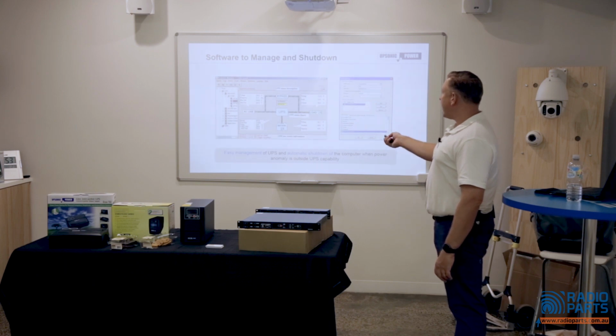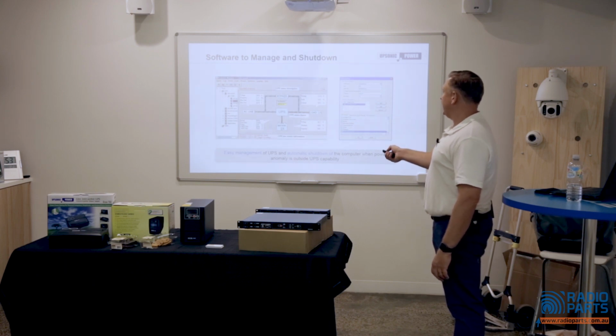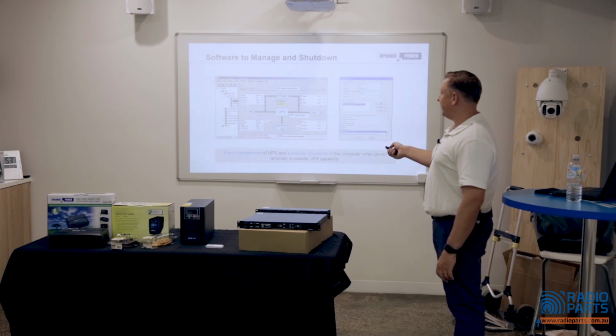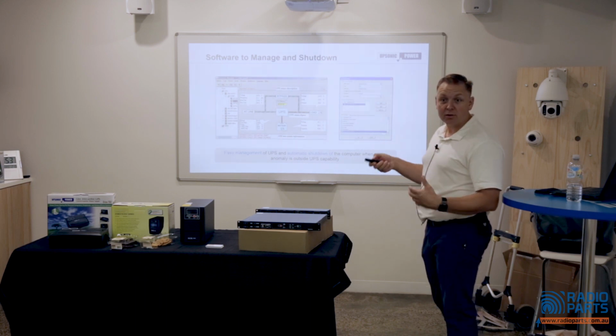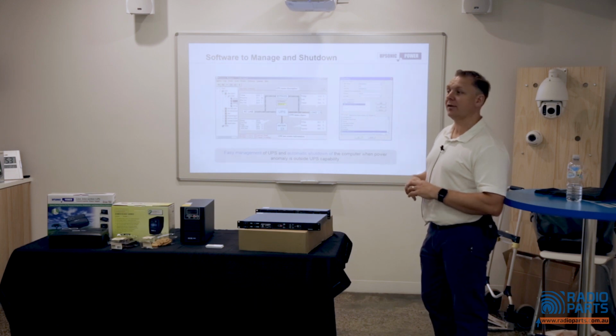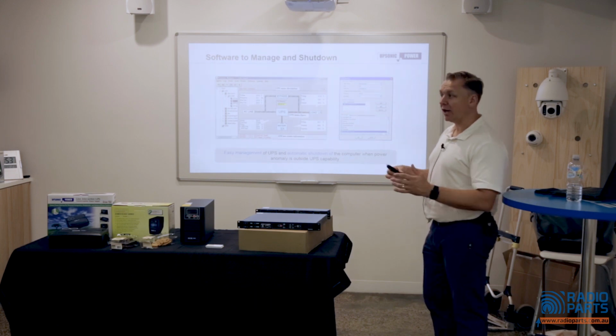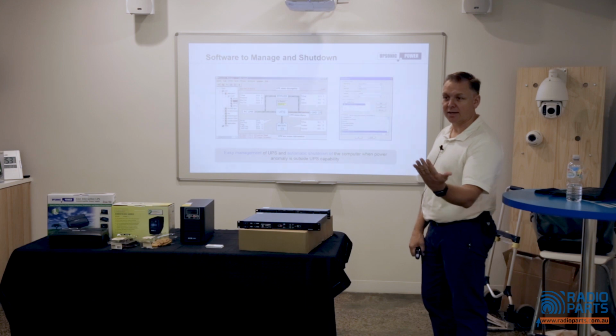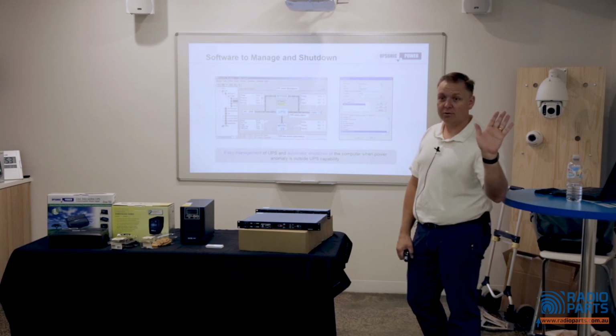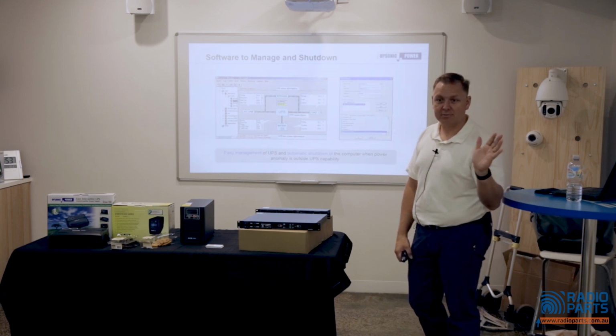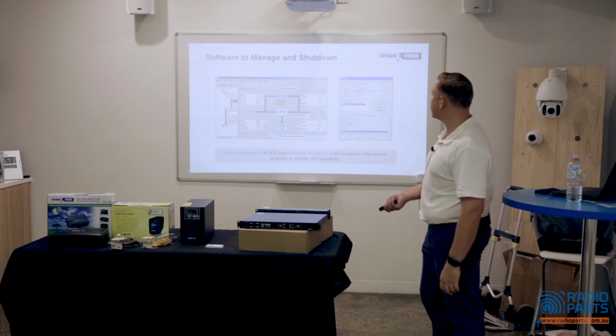You also get a little bit of a graph so you can see basically how it's working. You can also see how many times you get a mains failure, which can be an important negotiating point if you're having supply issues. You can go back to your UPS log and send that to your supply company and say, last month we had 16 failures, not good enough. You'd be surprised how often that happens.